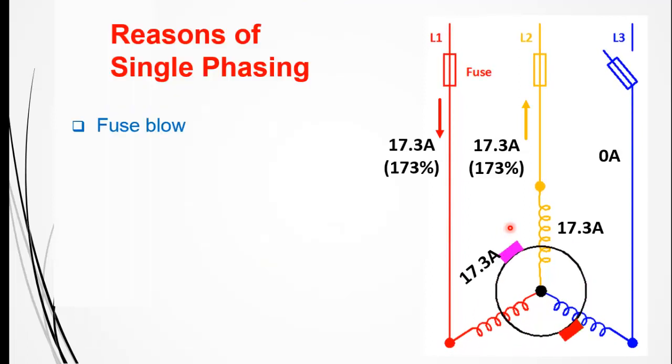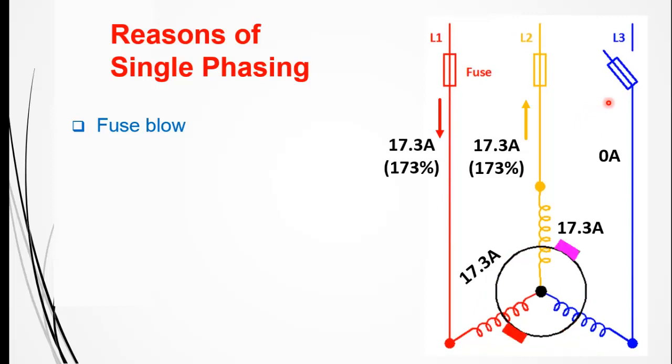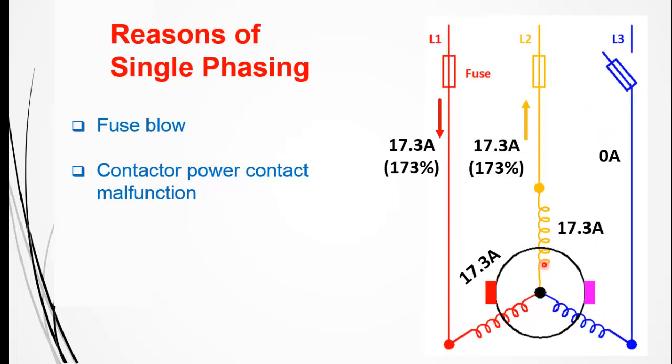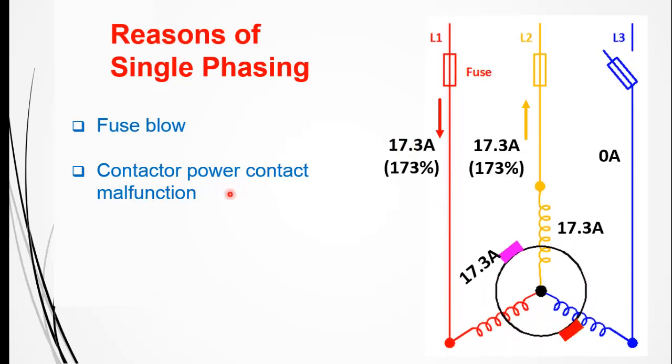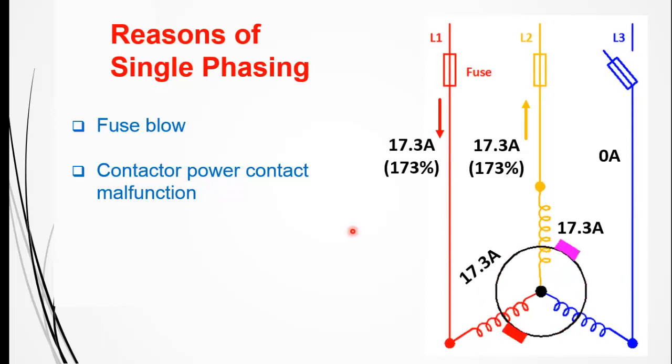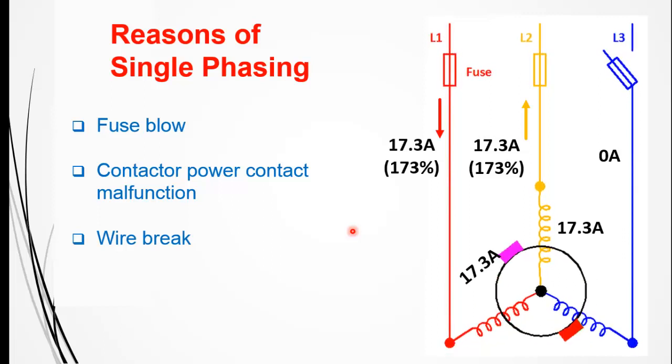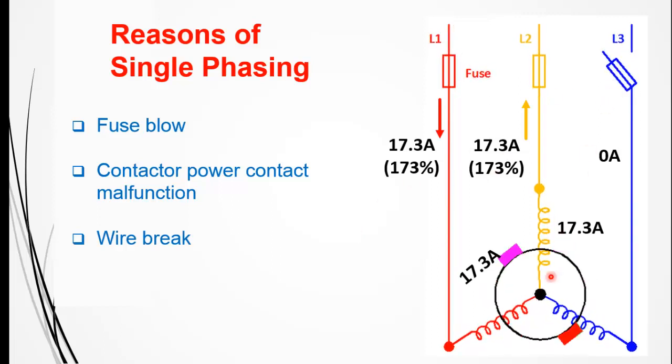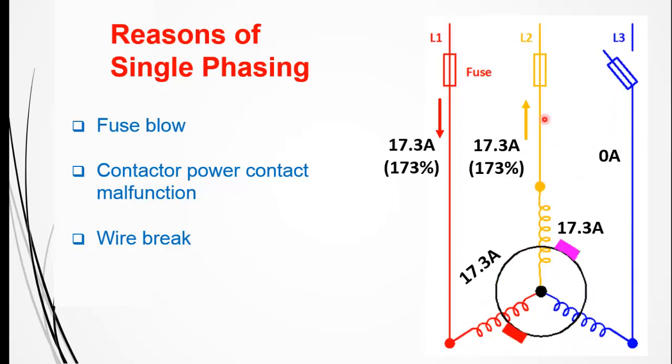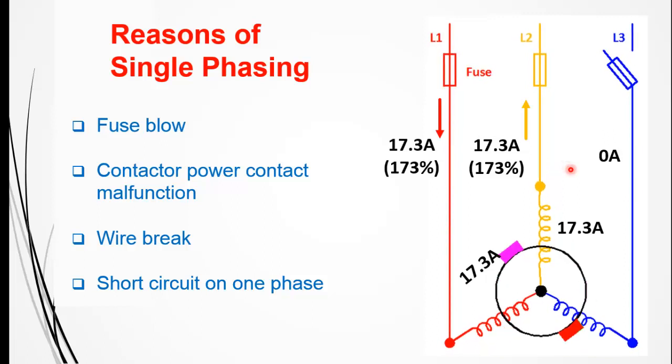Now let's talk about the reasons for single phasing. First, if one of the three fuses blows, it will cause single phasing on the three-phase motor. Another reason is if one pole in a three-pole contactor is damaged, which may also cause a single phasing problem. Also, a wire break from the feeder to the motor or from the grid to the distribution center. And finally, if a short circuit happens and it is not bolted, it will open one phase and cause single phasing.